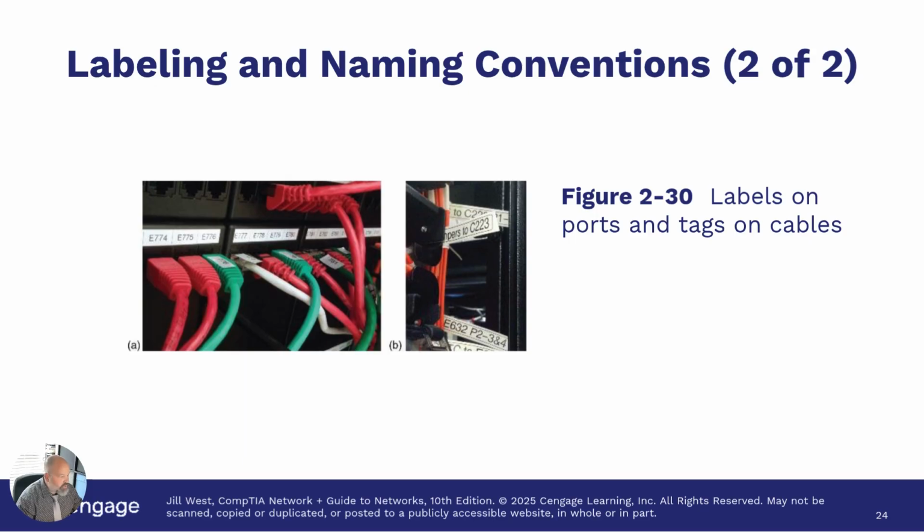Another thing that you can see is that the ports are clearly labeled with a naming schematic there. And notice that the tags are labeled as well. Those tags represent the purpose of the cable. Once again, you may think this is overkill, but if you're troubleshooting a problem in the middle of the night, you'll thank whoever took the time to label these properly. It's tremendously beneficial.